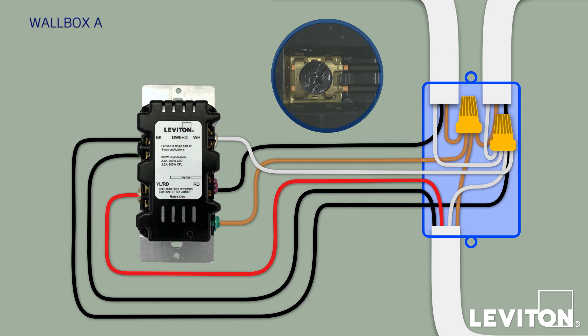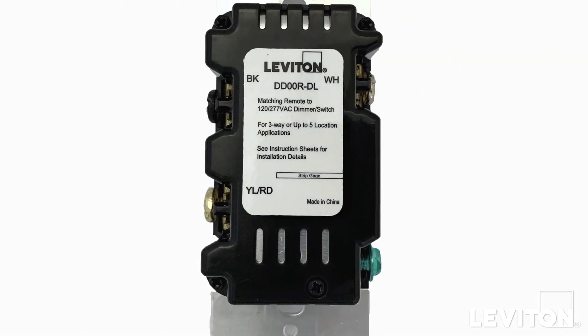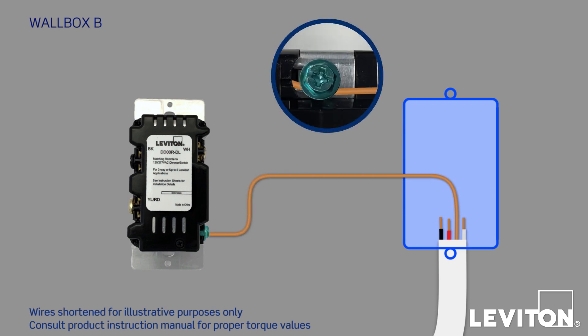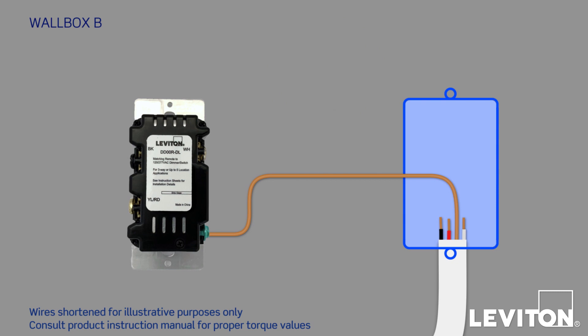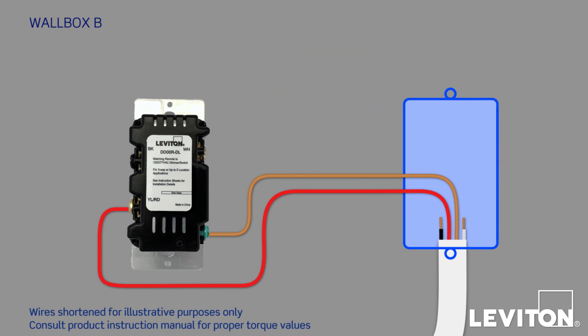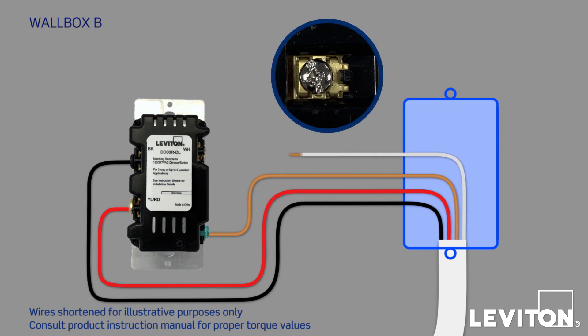Now let's install the remote device in Wallbox B — in this case, a Leviton DD00R-DL matching dimming remote. On the back, you'll see three screw terminals labeled BK, WH, and YL/RD, along with a green ground screw. All the wires within Wallbox B are coming from the three-conductor Traveler bundle. First, firmly connect the bare copper wire to the green ground screw on the device. Now connect the red conductor to the YL/RD terminal. Next, take the black conductor and connect it to the BK terminal. Finally, take the white conductor and connect it to the WH terminal.